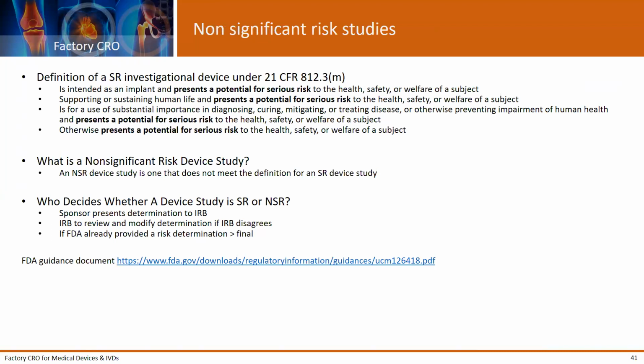I am not necessarily telling that the FDA is very expensive, but the time that comes with reviewing and approval of clinical trials is very long. So if you can do a study for a device that does not present a potential risk, according to the definition, you can start your clinical trial without the involvement of the FDA. But obviously you need to go to an IRB and you need to apply for a non-significant risk study. There is also a guidance document for this.